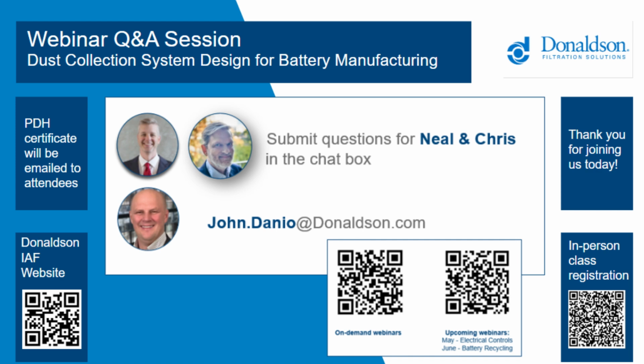Thank you. All right, so this one's probably for Neal. What would you say are the most common issues with dust collectors in the business? Issues like holes in the filters, breakdown of the fan. What are some of the more common issues? I would say the most common issue that we see is around the cleaning of the filters. These systems are typically designed to clean on demand. Once the differential pressure hits a certain high set point, the pulse cycles will begin and they will stop at a low set point.